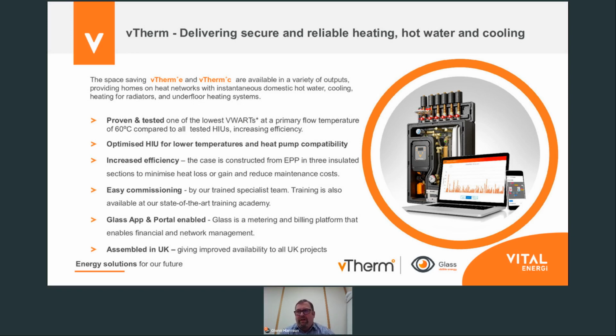Over time, the HIU communicates through a number of different mediums. It has its own inbuilt communications module, which communicates over NB-IoT, MBus, Ethernet, GSM - a number of ways to get the data out of the assets. Access to that data is absolutely critical in understanding whether the machine is delivering what we expect it to do. That also gives us the ability to understand how the unit works in practice, and how the network design as a whole is performing.